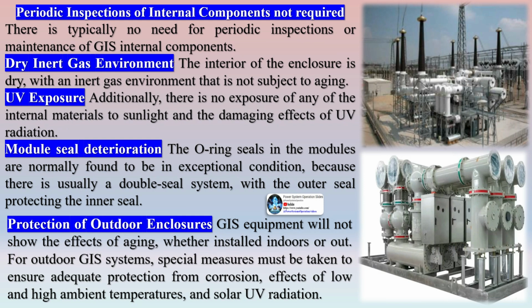There is typically no need for periodic inspections or maintenance of GIS internal components. Dry inert gas environment. The interior of the enclosure is dry, with an inert gas environment that is not subject to aging. UV exposure. Additionally, there is no exposure of any of the internal materials to sunlight and the damaging effects of UV radiation. Module seal deterioration. The O-ring seals in the modules are normally found to be in exceptional condition, because there is usually a double seal system, with the outer seal protecting the inner seal.